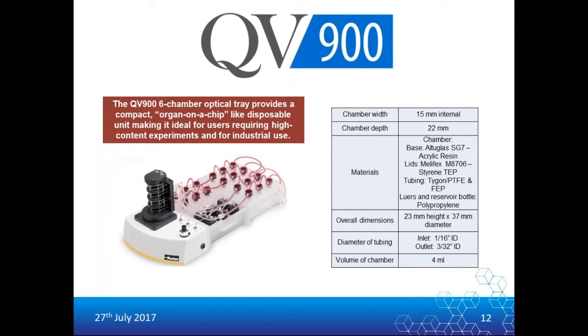On the right-hand side table here, we've got some details about the chambers themselves. The main difference between the 900 and the 500 and 600 is the material that it's made from. In order to make it optically clear, we had to choose an acrylic plastic rather than the silicone, which is what the 500 and the 600 are made from. This means that it's one use only, so you can't autoclave and sterilize this chamber, whereas the 500 and the 600 can be run through the autoclave a few times, and they can also be sterilized with alcohol. The volume of the QV900 is around 4 mils.